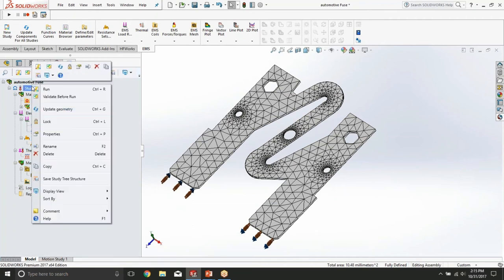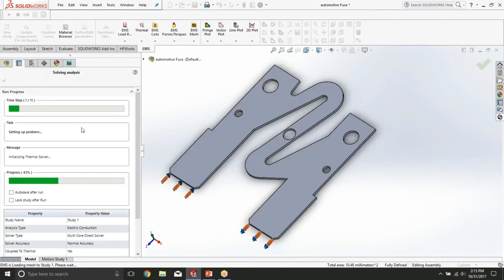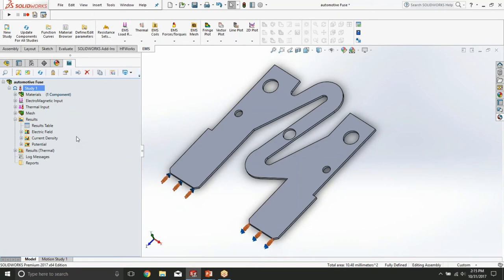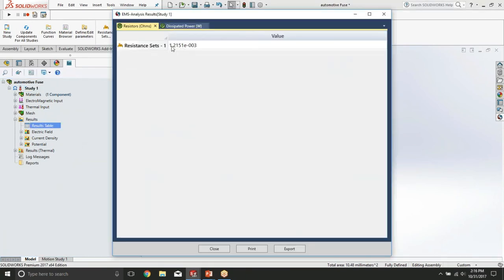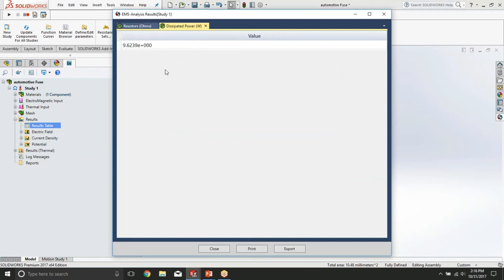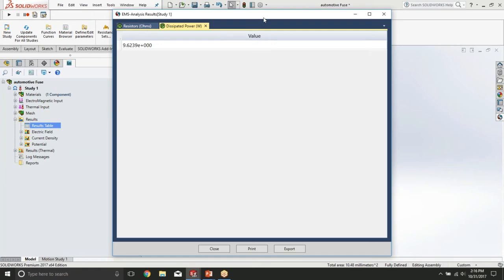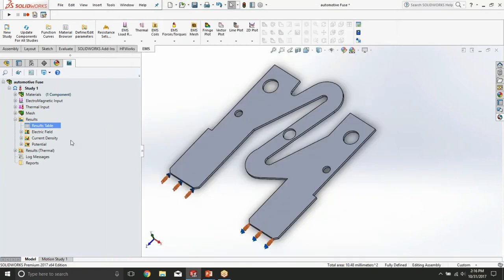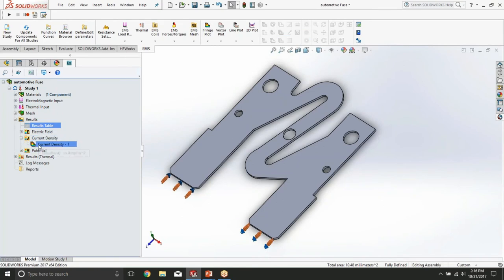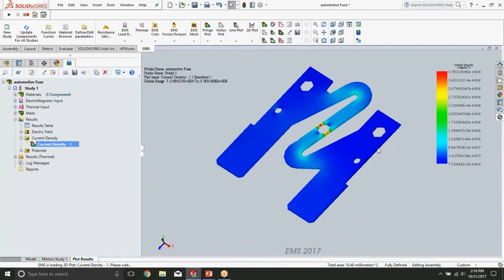So now we can just right click and hit run. After a couple of seconds we should see the results. First let's go to the results table and look at the resistance. Resistance is about 1.2 milliohms. Dissipated power is about 9.6 watts. For this resistance and knowing the voltage drop on the fuse, this tells us that we have about 89 amps of current going through the fuse.